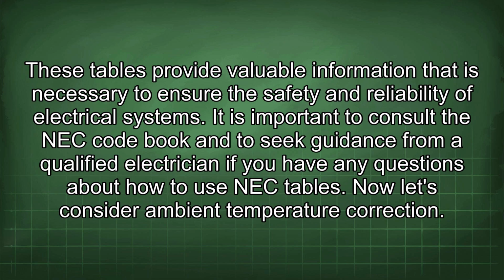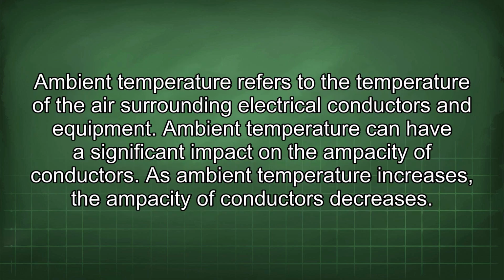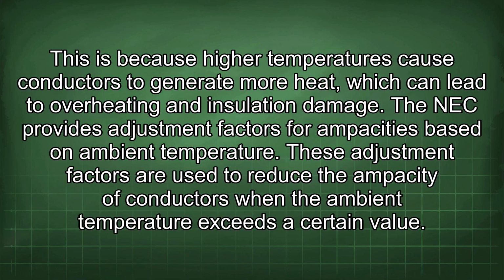Now let's consider ambient temperature correction. Ambient temperature refers to the temperature of the air surrounding electrical conductors and equipment. Ambient temperature can have a significant impact on the ampacity of conductors. As ambient temperature increases, the ampacity of conductors decreases. This is because high temperatures cause conductors to generate more heat, which can lead to overheating and insulation damage.